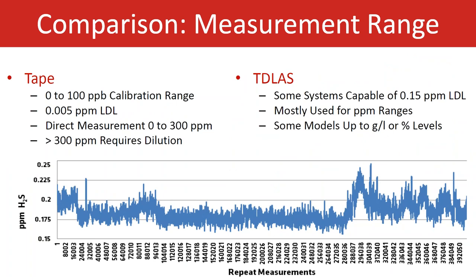In terms of measurement ranges, tape is really good for ultra-low measurements, such as 0.1 ppm or 100 ppb, with a lower detection limit of about 0.005 ppm or 5 ppb. Tape can also directly measure H2S up to approximately 300 ppm, and higher concentrations can be measured with dilution. For TDL, it's generally used for ppm ranges like 0 to 10 ppm H2S, with an LDL of about 0.15 ppm — very low, but still slightly higher than tape. However, some percent-level ranges can be offered with TDL as well.